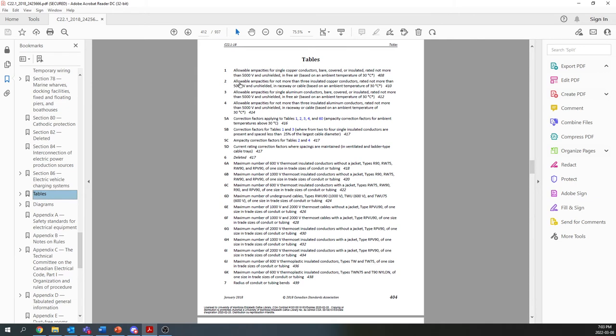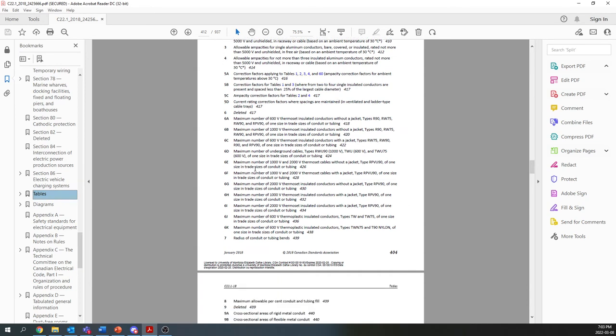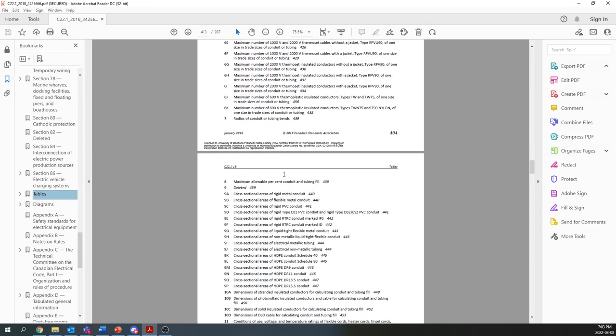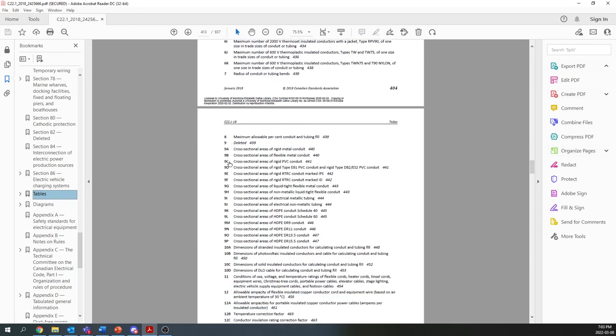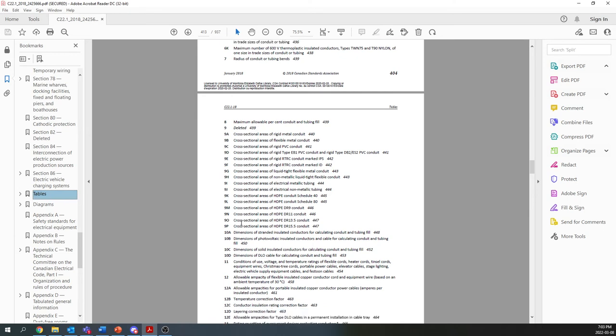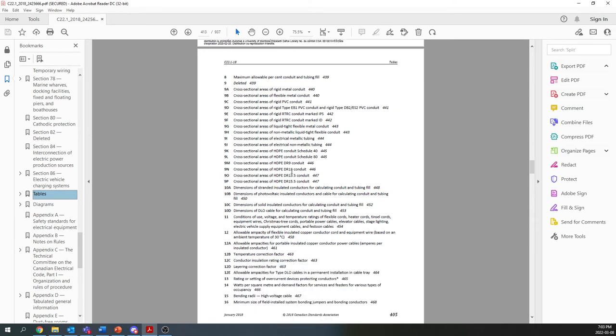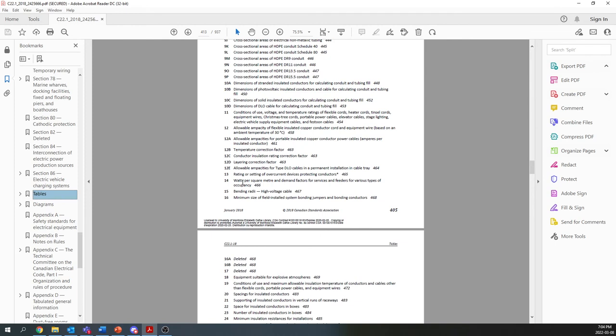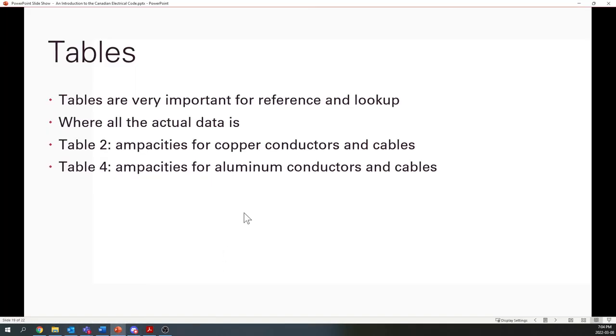Ampacities, like I was talking about, tables 1, 2, 3, 4 are very important. Table 6 is the number of different types of conductors that can be used in a tubing. Table 9 is cross-sectional areas. Table 10 is conduit fill and that sort of thing. So lots of different information here, very important, and if you're using the code every day, you're going to be referring back to the tables all the time to get information. So again, that's where all the actual data is.